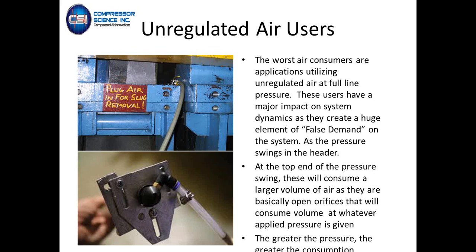less at 80 psi. But it becomes a vicious cycle, because in the mix of all that, you're trying to feed processes that have a dedicated consumption use to run your process equipment. So obviously, wherever you can regulate compressed air, usually we recommend, if you can do it at the source, fantastic. If you can lower the overall plant pressure down to 80 or 90 psi, that's great. Because what happens is when you have a process that has a regulator on it, and you think you're regulating that down to 60 psi from 100, well, we've actually seen systems that are swinging from 80 to 100.